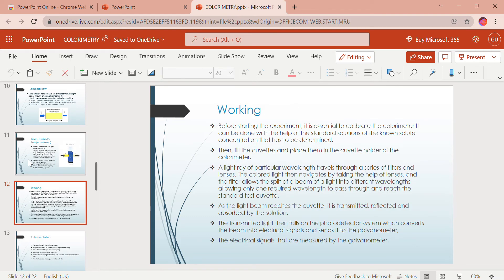For the working of the colorimeter: it is essential to calibrate the colorimeter before starting the experiment, using standard solutions of known concentration. The cuvettes are filled and placed in the cuvette holder. A light ray of particular wavelength travels through a series of filters and lenses, allowing only the required wavelength to pass through to the cuvette. As the light beam reaches the cuvette, it is transmitted, reflected, and absorbed. The transmitted light falls on the photodetector, which converts the beam into electrical signals sent to a galvanometer and displayed on a digital output device.